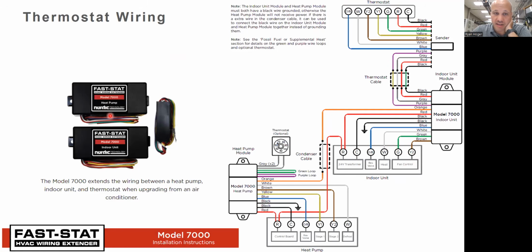So you get these 2 bigger boxes, and the 1 little box in this kit. All right, remember, you're only doing this if for some reason you can't pull new wire with additional conductors. Maybe they got fancy finished ceilings and you can't touch them or whatever it is. So the thermostat gets this little box put behind it. And what that guy does is it grabs a few of these wires from the thermostat and digitally combines them into 1 signal and sends them over some of the other wires.